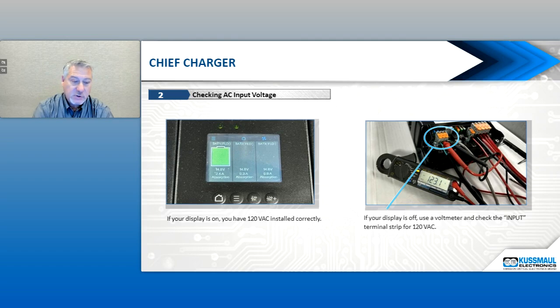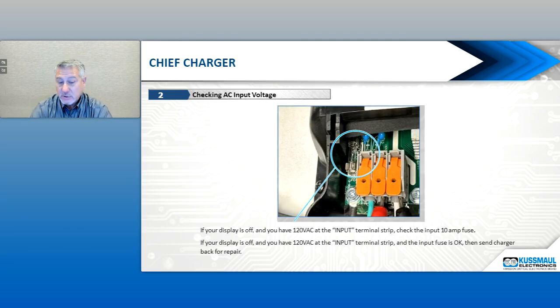The Chief charger has a touchscreen display on the charger itself. If that is on, you know you have 120 volts coming into the charger. If you have 120 volts coming in but the display is not on, check the small 10 amp fuse right by the 120 volt input to see if it's good. If the fuse is good and you have 120 volts coming in, that charger needs to be sent back to Kussmaul for replacement or repair.